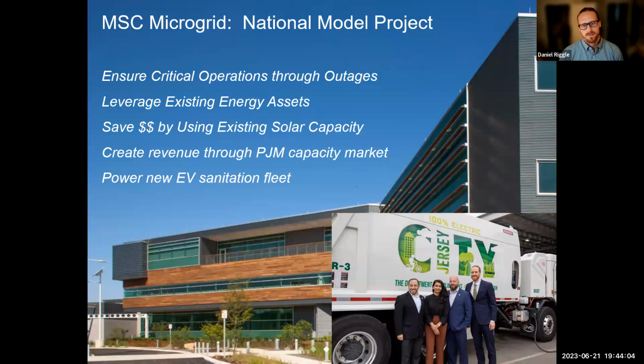Really one of the highlights for this project is the microgrid that we're installing at MSC, the Municipal Services Complex, also known as DPW, 1315 Linden Ave East. It's a newer building where the city runs a lot of its emergency operations. They do have a large backup generator, and a large solar PV system there, about 1.2 megawatts. However, the way the system was set up, if the power goes down, the solar doesn't operate. And the generator was tied in only to emergency loads, which did not include some of their IT systems and phone systems. So they had an event where they realized they've got these assets, but they're not optimized to keep them running through power outages.